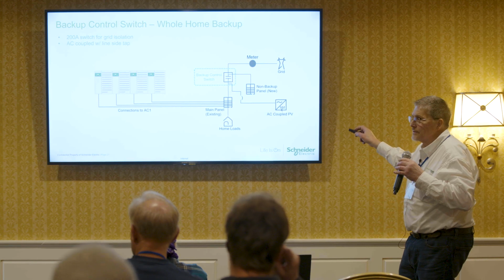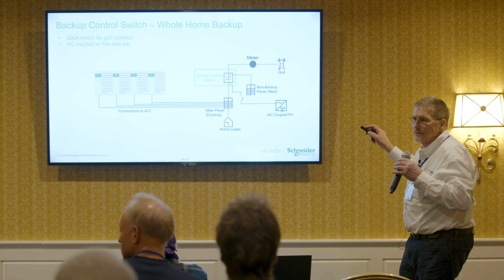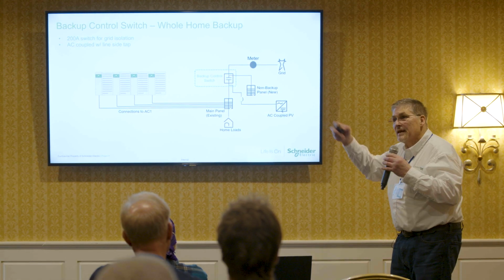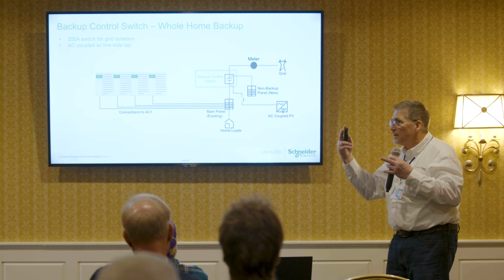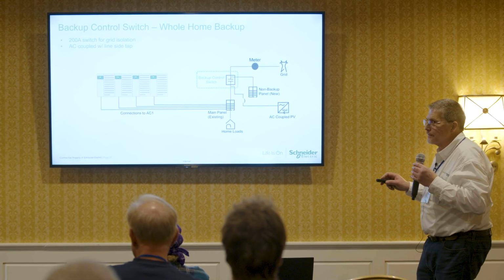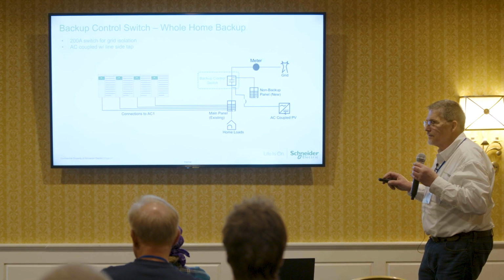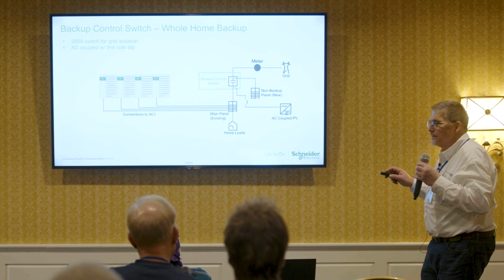It is. Yes. How would you shut down power coming through the BCS? You would have to shut down the power that was being sensed. We have the 2 sensing lines, right? So if you interrupt those sensing lines, it'll shut off that output power. So we hit a regular meter socket, we have that next to it, that gives us our line tap, it gives us our emergency disconnect.